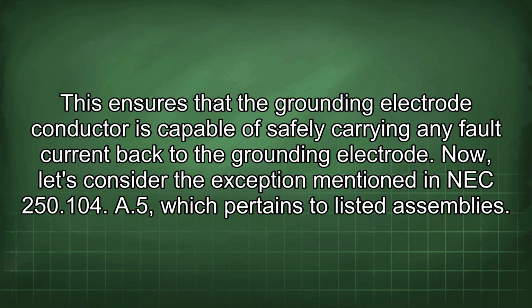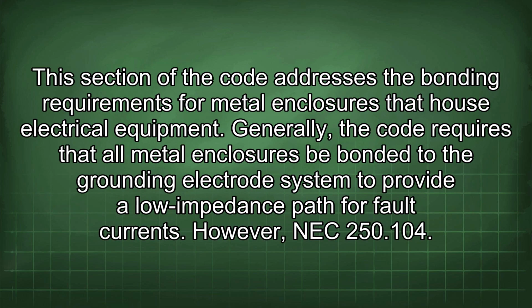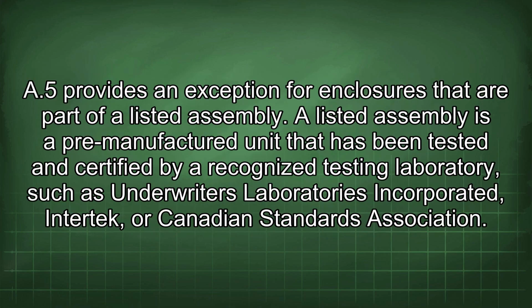Now let's consider the exception mentioned in NEC 250.104 A5, which pertains to listed assemblies. This section of the code addresses the bonding requirements for metal enclosures that house electrical equipment. Generally, the code requires that all metal enclosures be bonded to the grounding electrode system to provide a low impedance path for fault currents. However, NEC 250.104 A5 provides an exception for enclosures that are part of a listed assembly.